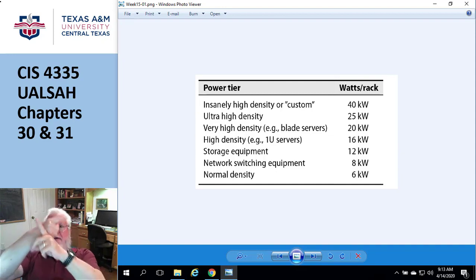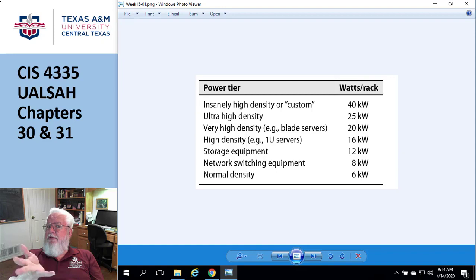They've done the math to figure out where the trough is—where you save the most money—and it's not 80 degrees, it's a lot hotter than that. So if you're trying to find an optimum solution based on money, it's okay to run things hotter than the design criteria, knowing the failure rate will increase. But if the repair cost is cheaper than the electricity for cooling, you come out ahead. Yes, a higher failure rate would ensue.